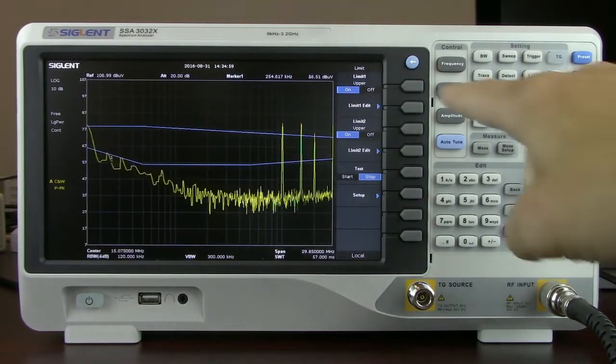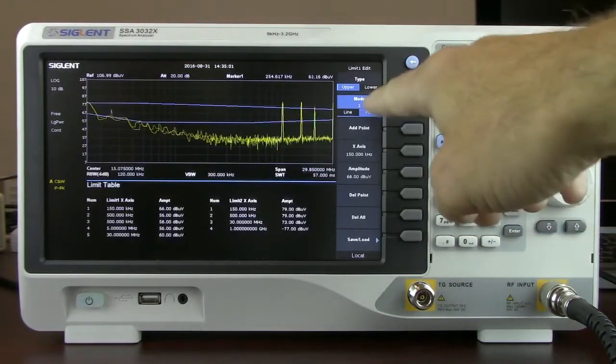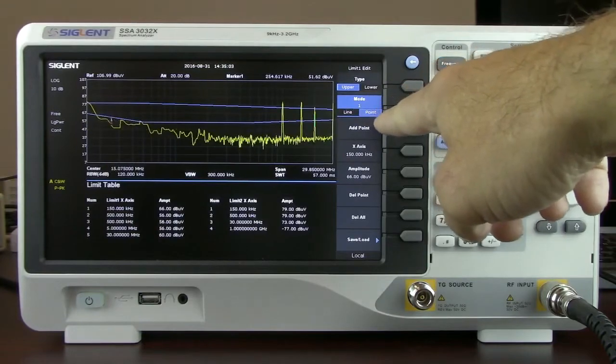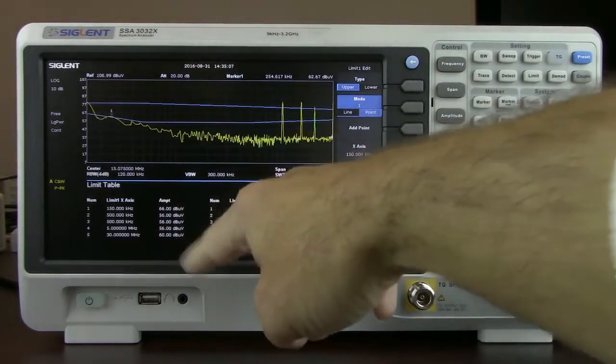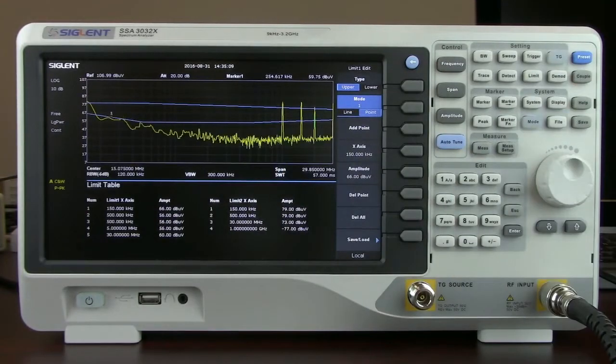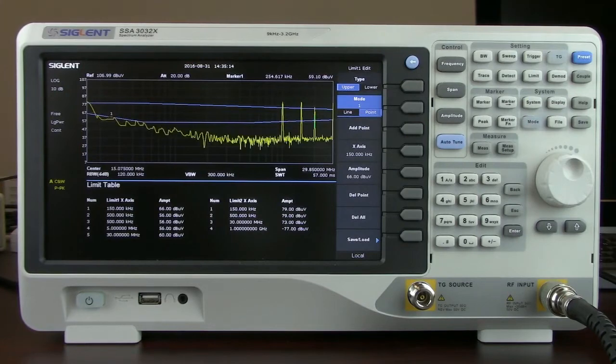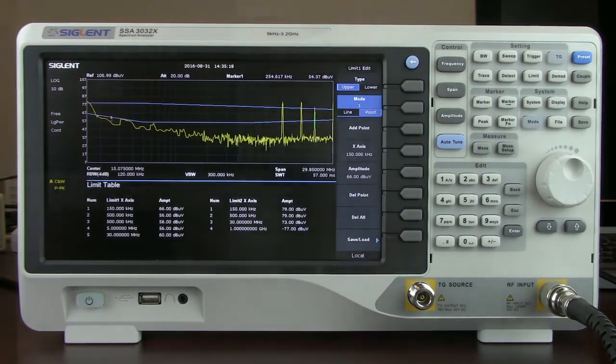Both of the limits can also be edited. They've got a line mode as well as a point mode. And in the point mode, you can see that we've got the X axis as well as the amplitude values for each of the points in that particular test. All of these features are very helpful when you're performing pre-compliance. And there's also a software application that can help to sequence a lot of the data collection.